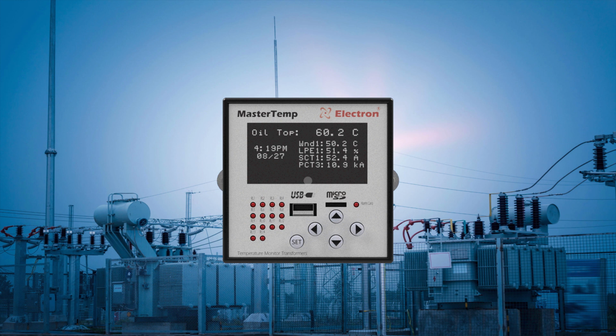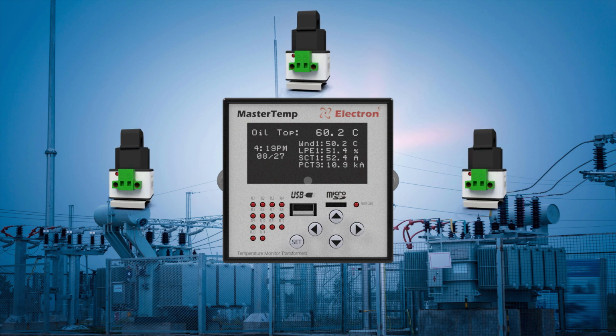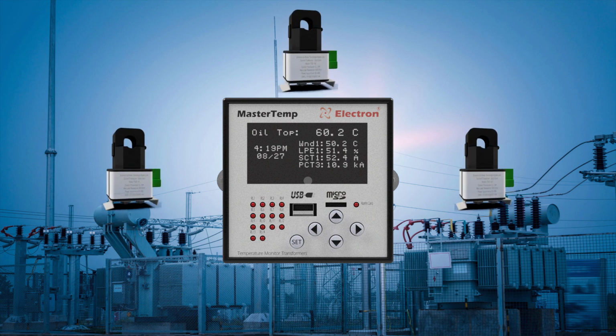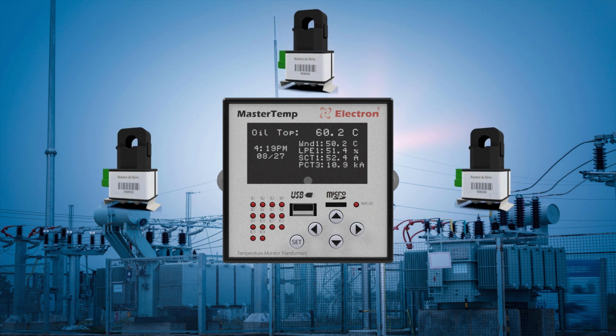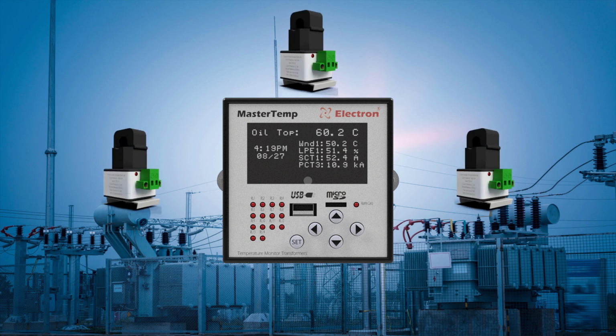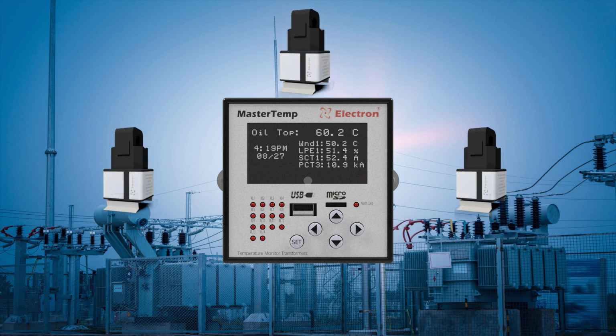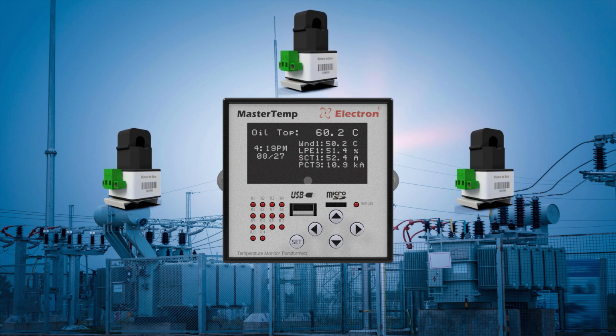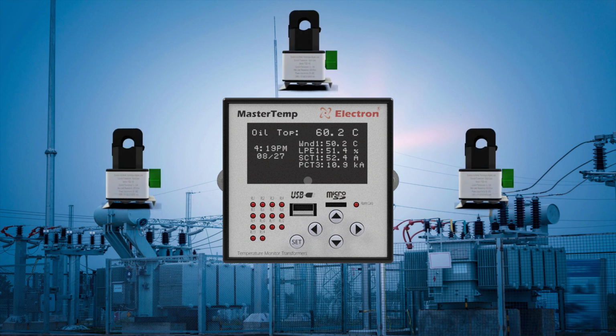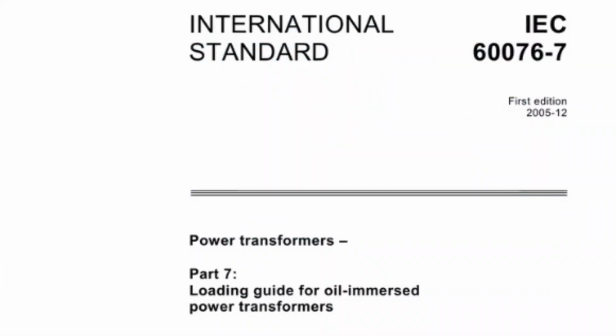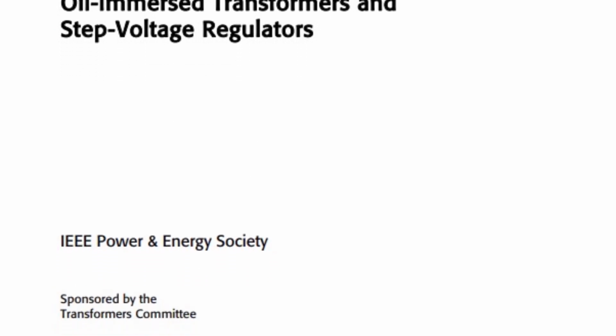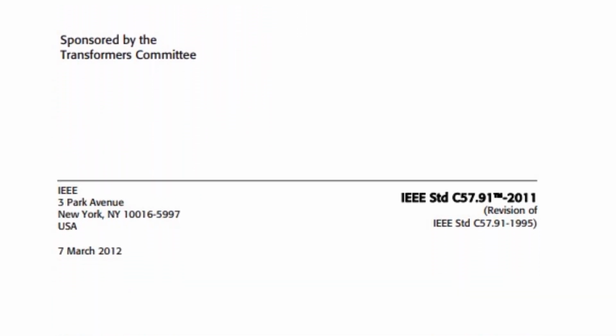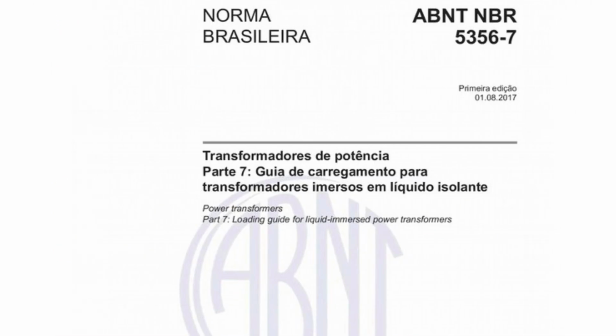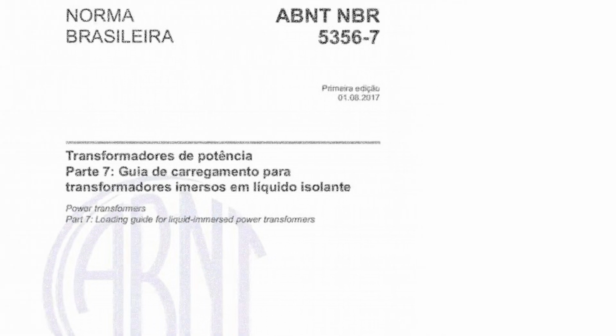In addition to the two inputs of type PT100, Mastertemp also has input for up to 3 split-core type current transducers, which are used to monitor the circulation current in each winding. To provide this information for the Mastertemp to calculate the temperature of winding, using the method based on IEC 60076-7 standard, IEEE C57.91 standard, and NBR 5356-7 2017 standard.